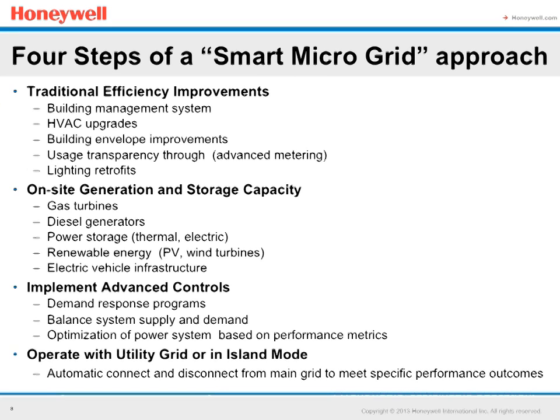Lastly, you want to be able to operate the microgrid in conjunction with the utility grid, or in island mode. Island mode means you're cut off, separated from the utility grid, fully operational as an island. You can also operate with the utility grid—you can bring your generation equipment back online to help the grid stabilize on hot summer days, for example, putting power back on the grid to help them out. There's a lot of operational capability built into these controls based on your local utility, what you wish to accomplish, and what the utility wants to sign up for. Those are the four steps we typically go through.